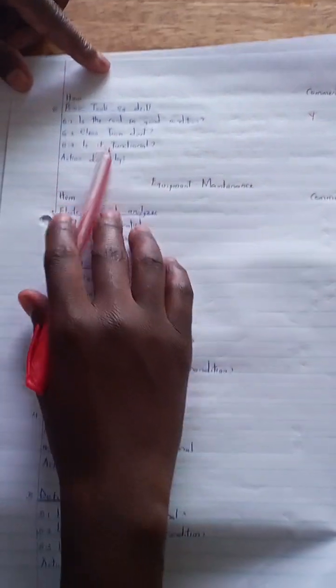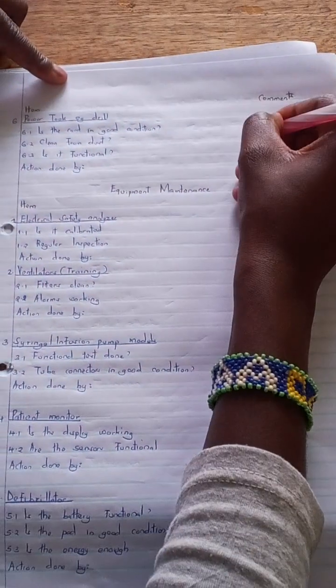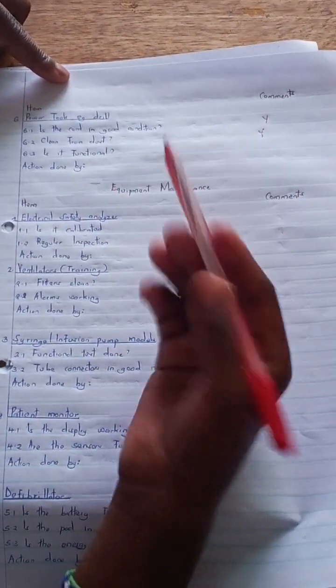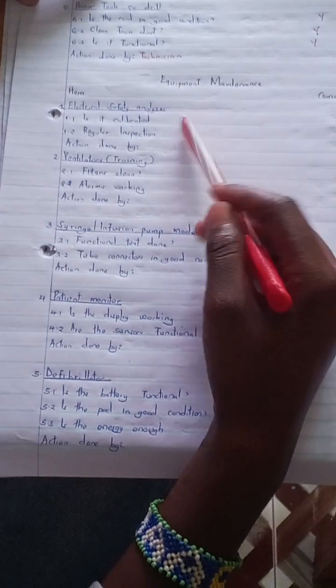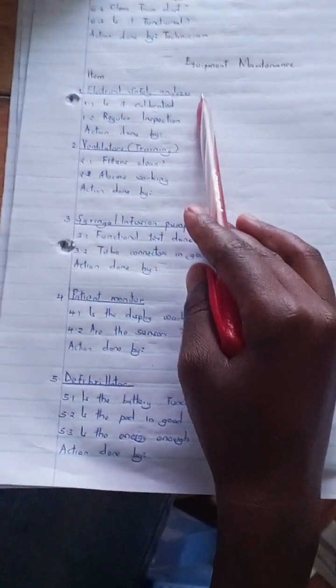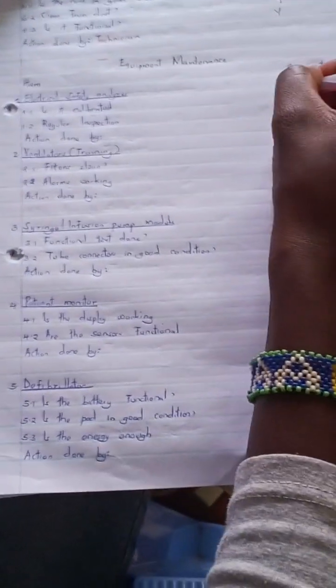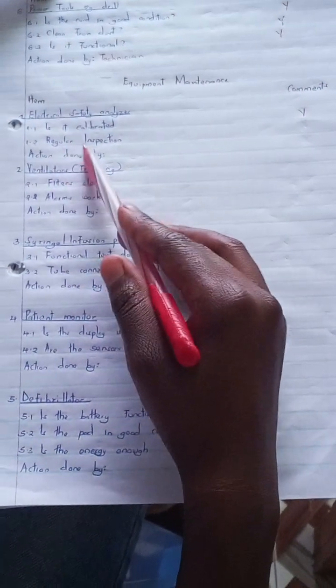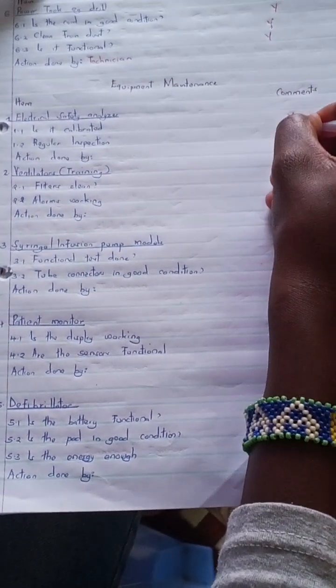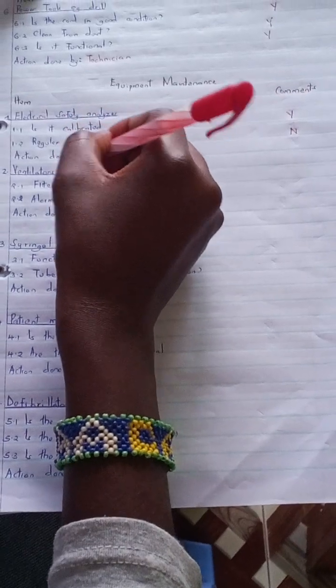Then we come to the power tools, e.g. the drills. Is the cord in good condition? When it is in good condition, we will say yes, that is our Y in our comment section. Is it clean from dust? Yes, that's Y. Is it functional? When it is functional, we will say yes. The action may be done by a technician. Then we go to equipment maintenance. We are done with the tools maintenance. The equipment number 1 is the electrical safety analyzer. Is it calibrated? When it is calibrated, we say yes. Was there regular inspection? When there is no regular inspection, we may say no. Action done by maybe an electrical engineer.